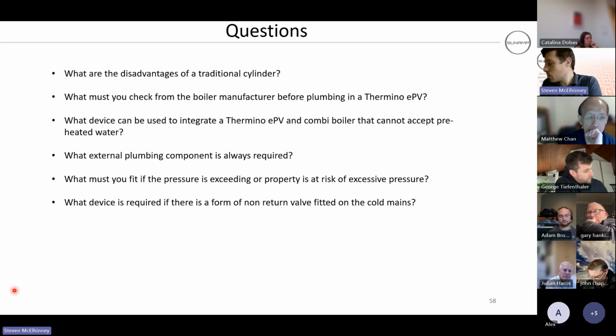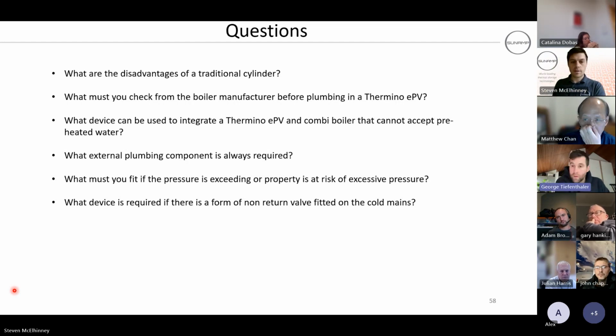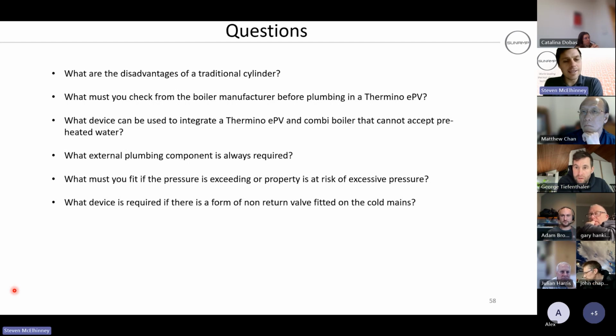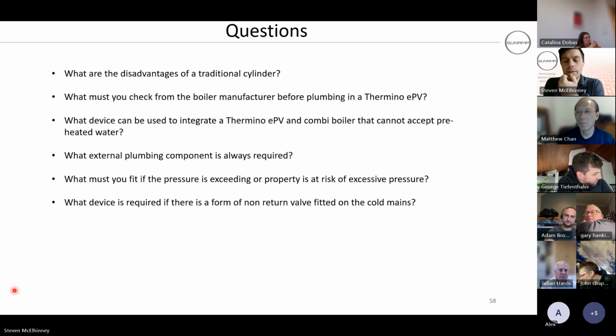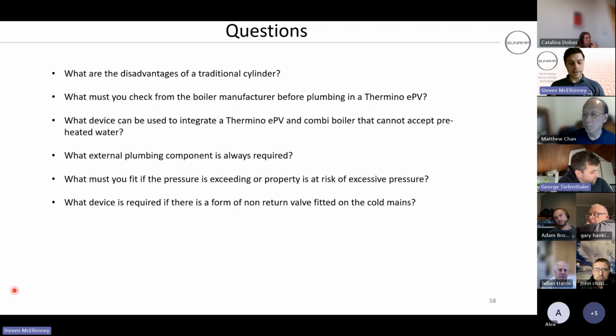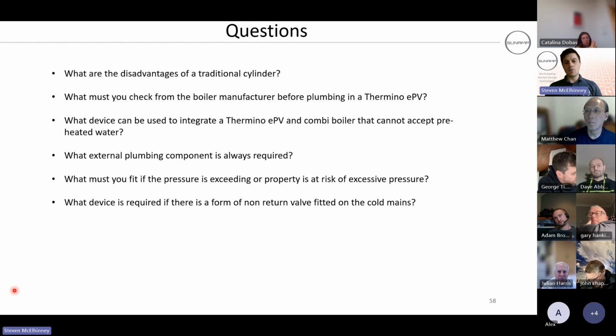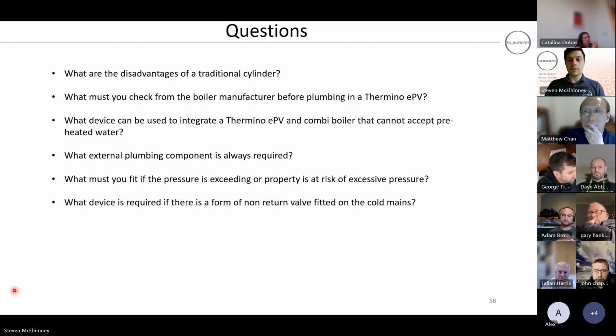What external plumbing component is always required? Expansion relief. Expansion something. Relief valve. Yeah, it's the expansion vessel, isn't it? 0.5 litres. Yeah, that's the one. Anything else? Pressure reducing. Non-return valve. What? Blending valve. Yeah, I was going to say, what might you get sued over if the customer burns himself? So yeah, blending valve, anti-scald device. So in an ideal installation, if you've got no non-return valves, you've got guaranteed 2.5 to 3 bar pressure coming into the property. All you're ever going to need is an expansion vessel and the TMV. What device is required if there is a form of non-return valve fitted on the cold mains?